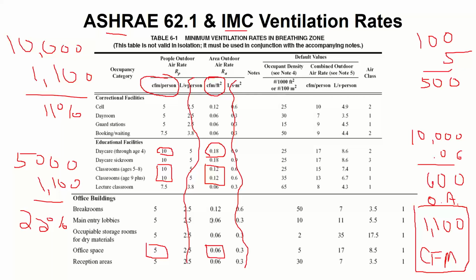You don't have to ventilate a building that's not occupied. If nobody's there, who are you ventilating for, right? So you only have to ventilate during the occupied hours. Now, many of us will program it so we start the ventilation like an hour before occupied just to purge the VOCs that have accumulated in there. But in general, it's during the occupied hours. And at nighttime, you don't have to do that. So you shut the ventilation damper, preferably leave it shut, although most buildings make the mistake of not doing that. Leave it shut, and then turn the fan on only if the heat or cooling needs to come on. Hopefully that answers the question, Greg.